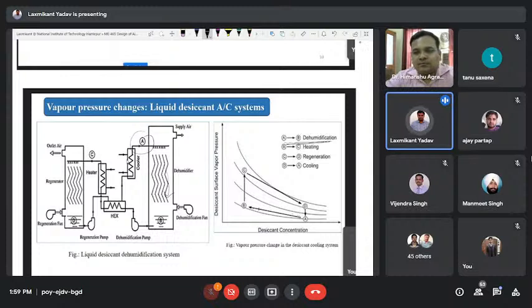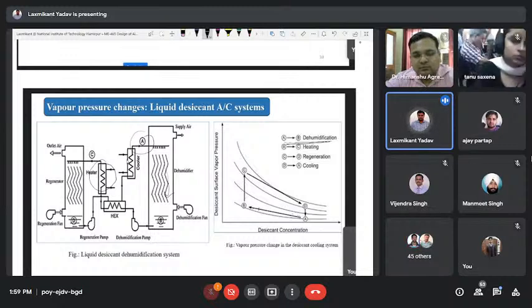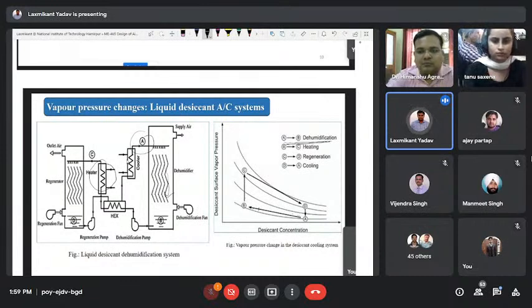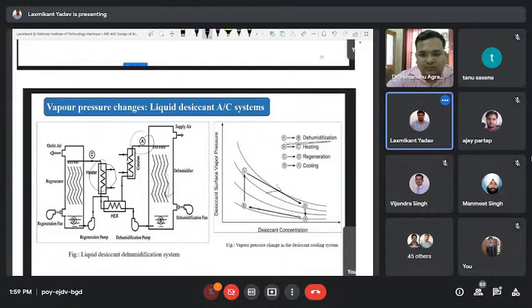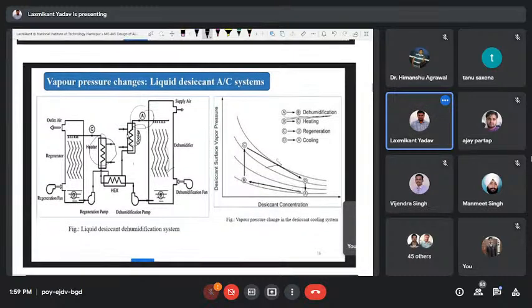B to C is where the heater is required, so there is constant concentration, but the vapor pressure increases. Then C to D, again there will be a change in desiccant concentration because of the removal of moisture. And D to A, where is D to A? D to A is the cooler, so cooling. So this is the vapor pressure versus concentration diagram of liquid desiccant.